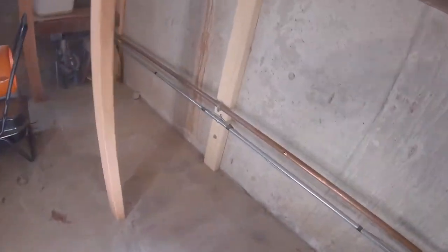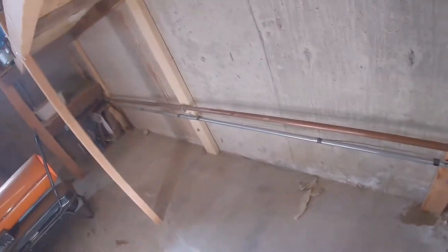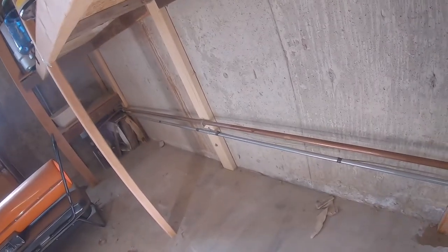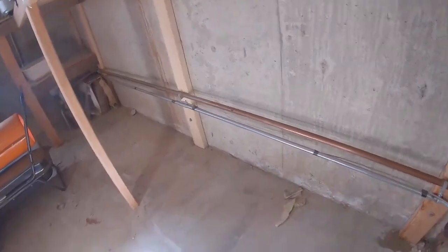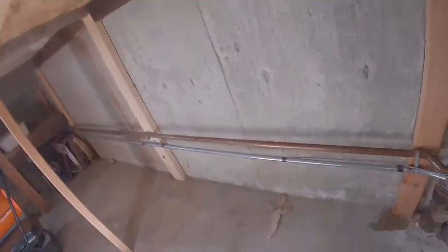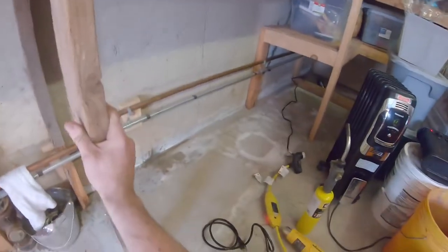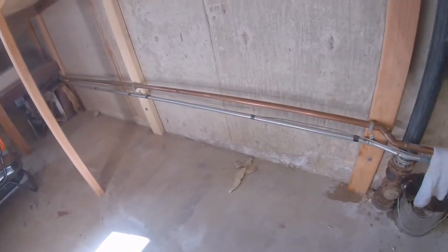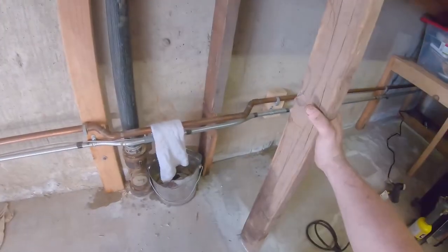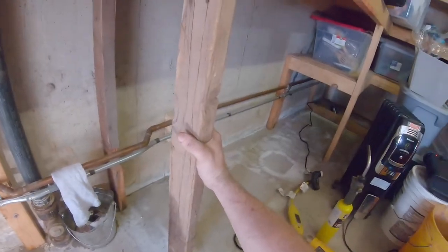The other important thing when doing the freeze break is make sure that all the water fixtures in the home are turned on. When this thaws out, if this was a city main for example, it would shoot that ice particle down the line. That can cause issues. So definitely make sure that you have all the pipes open. Also, the thermal expansion within the pipes when they're frozen can also cause further damage if nothing is left open inside the home.